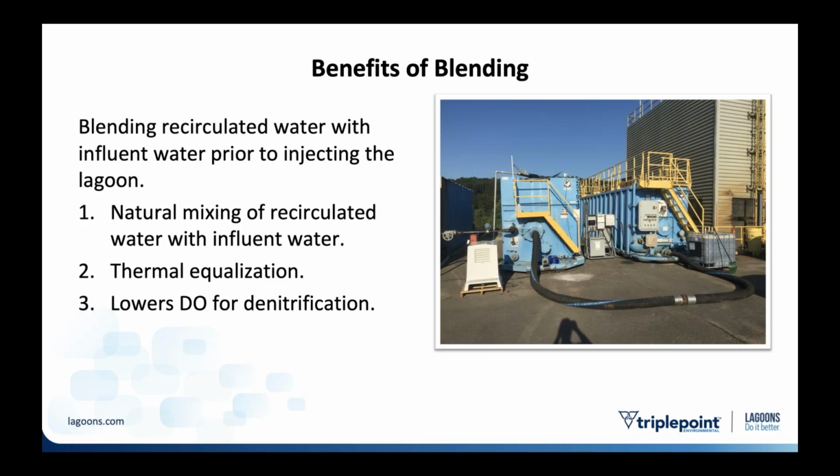So they had some ammonia, so what we did was we had the nitrification tank there on the left, the denitrification tank on the right, and we ran the system. The water came out of the back of the denitrification tank, flowed 500 feet to a storage lagoon, and boom, it was done, right? That was supposed to be one pass, done. So we started the system up, and we were having all sorts of issues with pH and all these different factors to get nitrification, get the denitrification to work. The DO was too high, and all manner of things. We learned a lot on this project. Eventually, we sorted out all these issues.